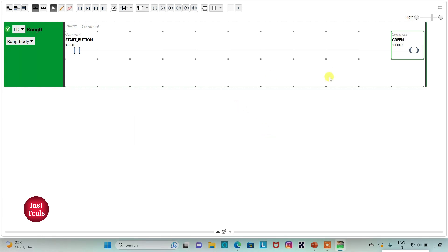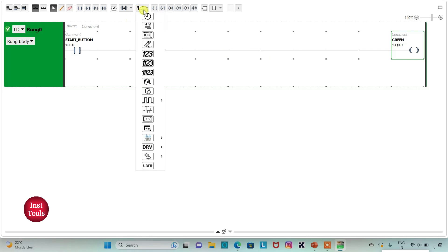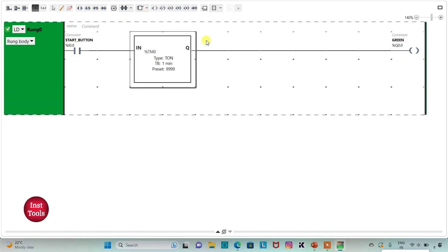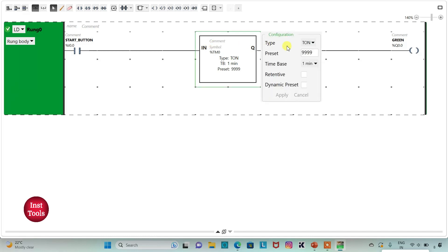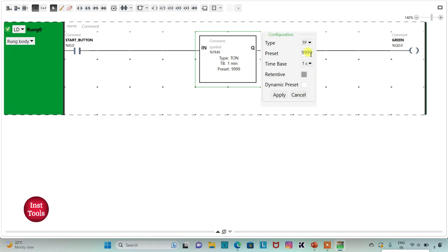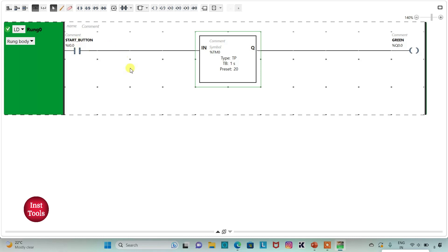The green light should be on for 20 seconds, so I will insert a functional block timer. I will select TP with time base as second and preset value as 20, then click Apply. When the start button is pressed, the green light will turn on and stay on for 20 seconds.